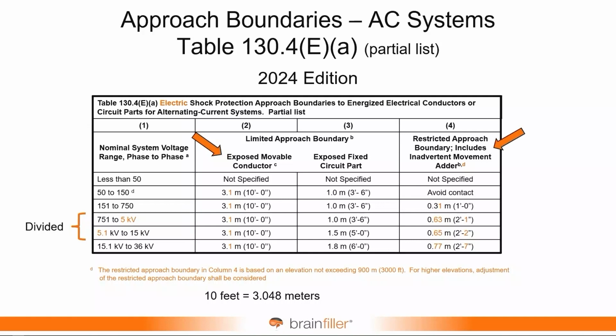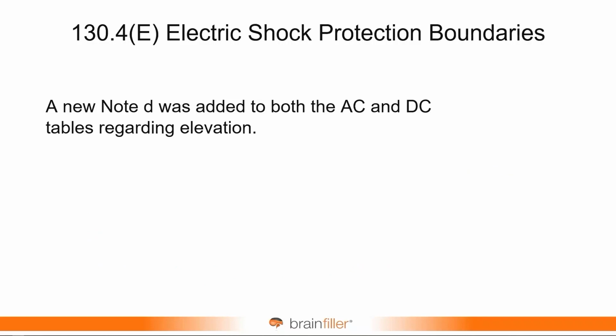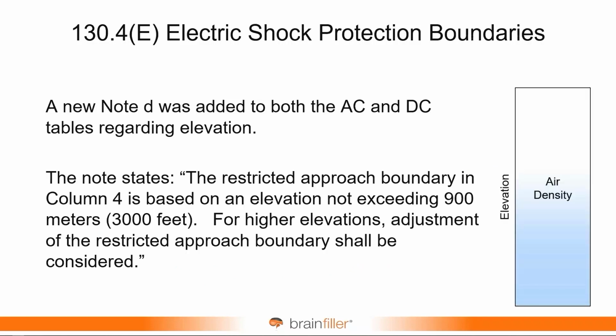And then over here, the restricted approach boundaries were modified a little bit to harmonize with the minimum approach distances within OSHA. And then there's a new note that was added. And this note is about elevation. For higher elevations above 3,000 feet, you may want to consider modifying or adjusting the restricted approach boundary. Why would you do that? Because at higher elevations, the air becomes less dense. So the dielectric strength of air becomes lower as the air density becomes lower. And a lot of electrical equipment does have derating factors once you get above 3,000 feet.